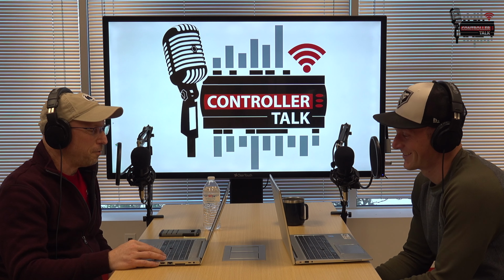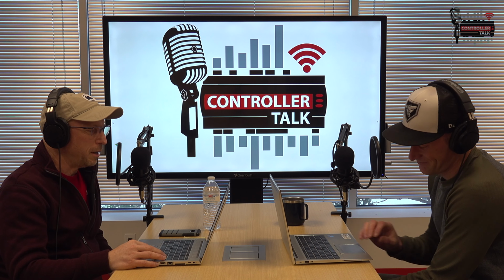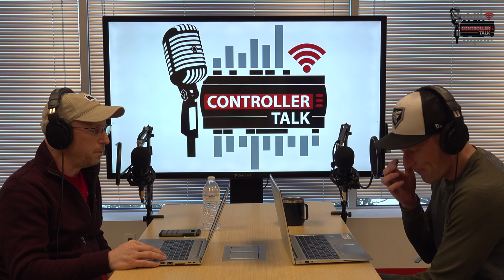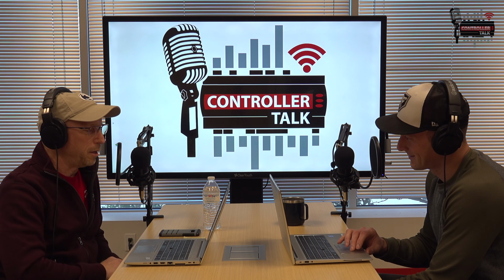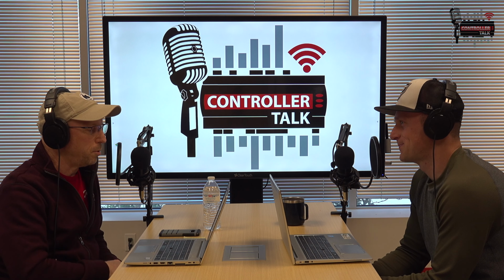Hey, since this is our first recording of the new year, let's tackle a topic head on that sometimes confuses people that are setting up or troubleshooting things that use a variable output, like a variable speed compressor, digital compressor, or even variable speed condenser fans. There's lots of other uses for the variable output, but we're going to focus on those today. Some people call them analog outputs too. They normally send a variable DC signal out of a board to a device in the range of 0 to 5 volts, 0 to 10 volts, or 10 to 0 volts.